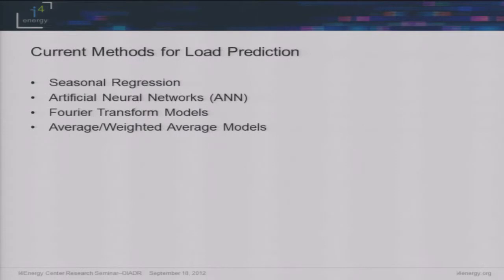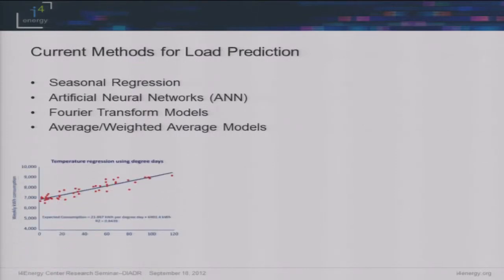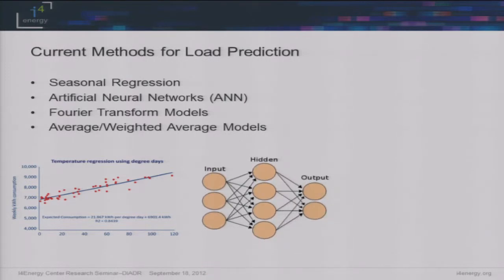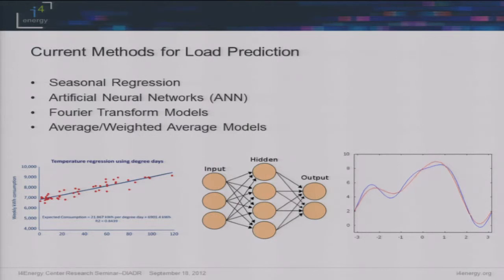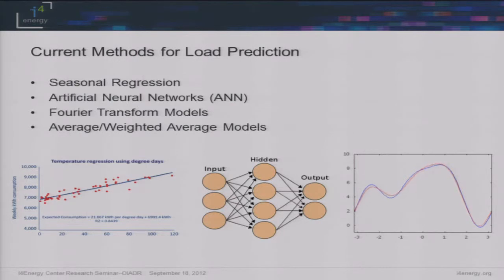There are current methods for load prediction that we see often: seasonal regression or temperature regression, basically looking at different parameters and trying to fit data. A lot of times you see piecewise regression models — this is a linear temperature regression just trying to make relationships. You also see artificial neural networks, which are a little more complex with a hidden layer. And then there are Fourier transform models. Each of these has been explored: Lawrence Berkeley National Labs has done regression models, artificial neural networks have been used extensively in power markets, and Texas A&M developed a Fourier transform model.